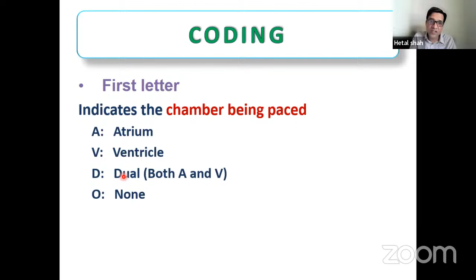So if it is written, A stands for atrium, V stands for ventricle, D stands for dual, and O stands for none. It is very unlikely that the first letter will be O, so it will be either A, V, or D. Either the atrium is being paced, the ventricle is being paced, or dual, where both chambers are getting paced. So the first letter indicates the chamber being paced.